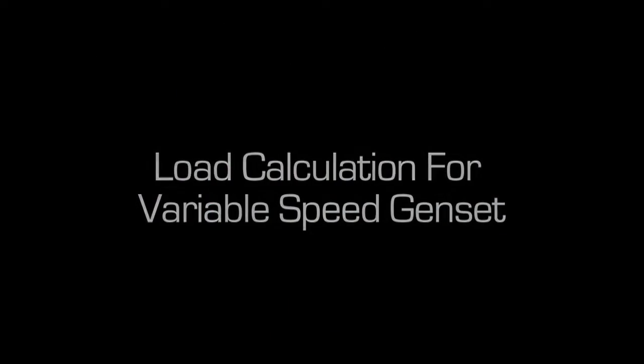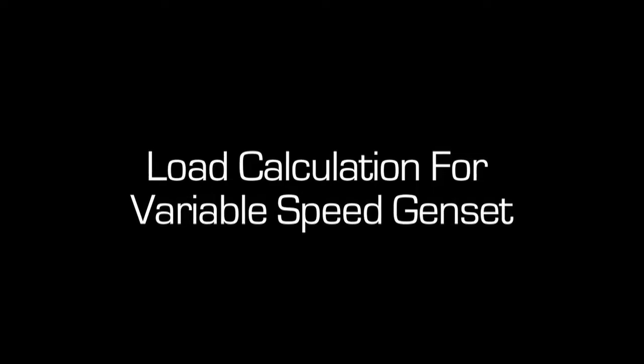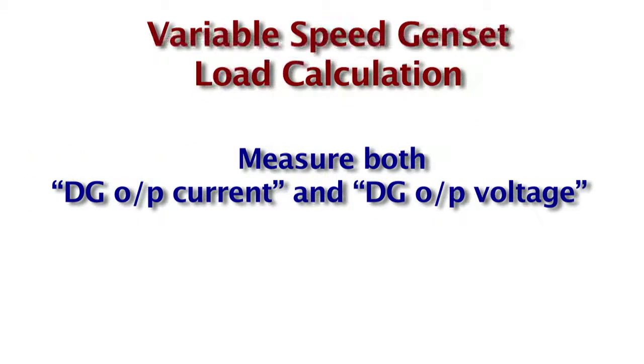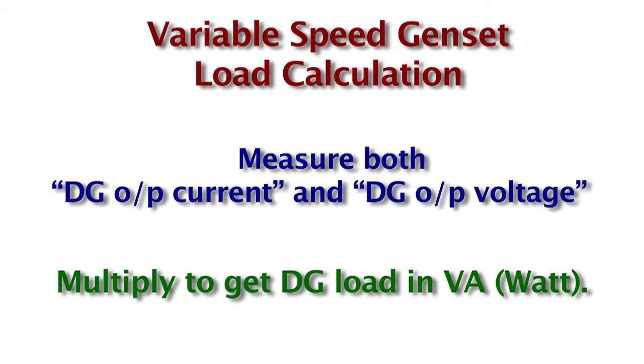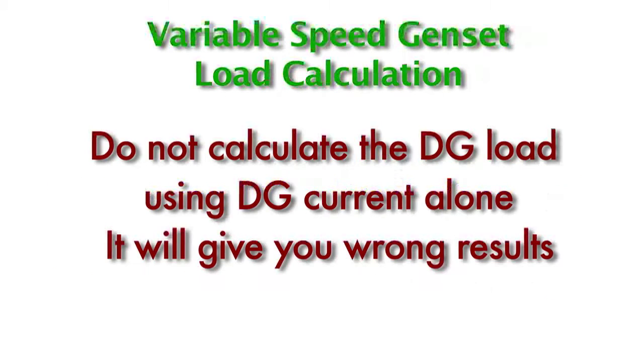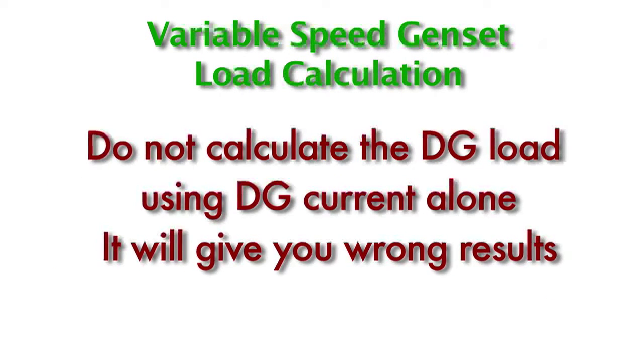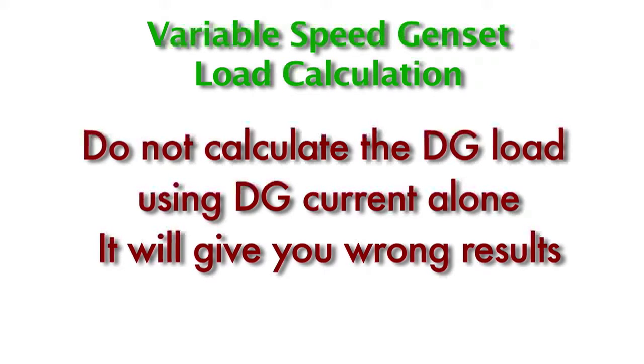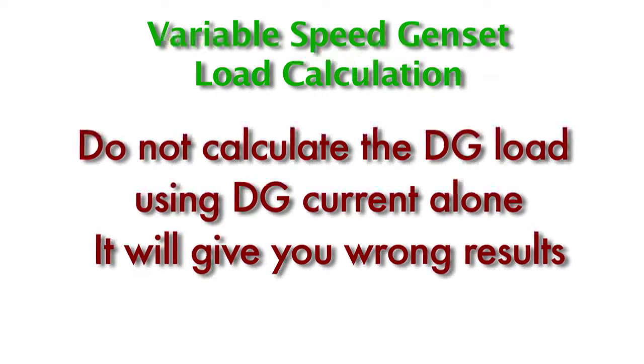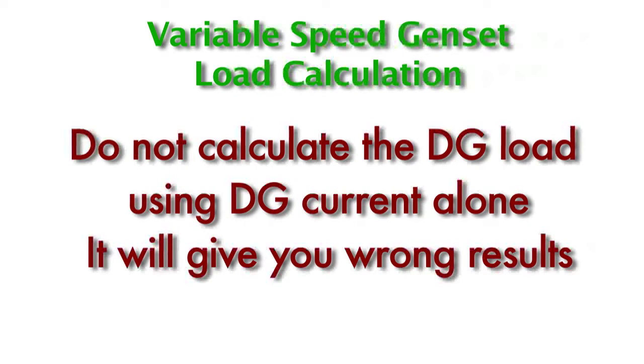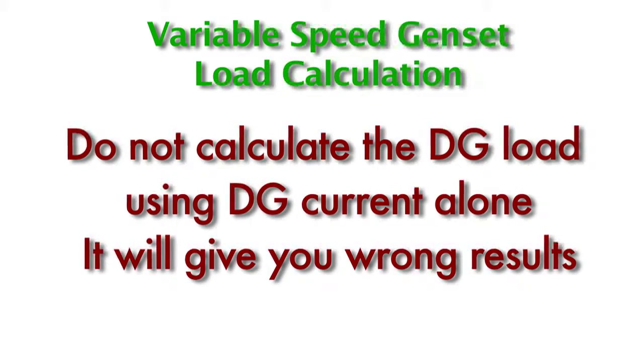If you want to know the load on a variable speed genset, you need to measure both the DG output current and the DG output voltage. You need to multiply them to get the DG load in VA, watt. Do not calculate the DG load using DG current alone, like you do in case of a fixed speed genset, because that method can give you wrong results.